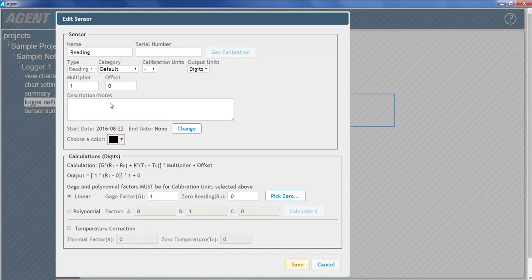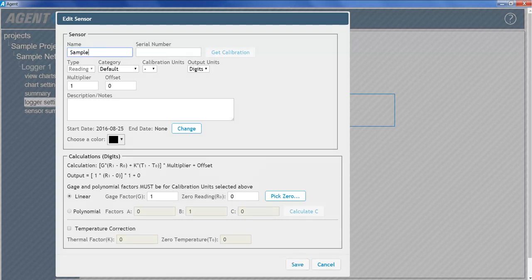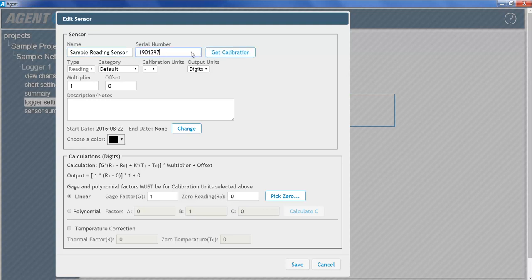Start by giving the reading sensor a name, then enter the serial number of the vibrating wire sensor connected to the logger. Clicking the Get Calibrations button will retrieve the calibration factors for the specified serial number from Geokon's online calibration database. This feature is only available for certain sensors manufactured after 2016. Refer to the agent manual for more information.